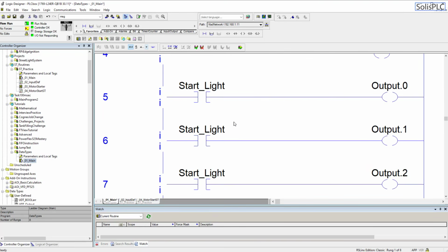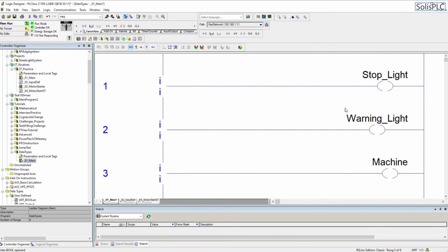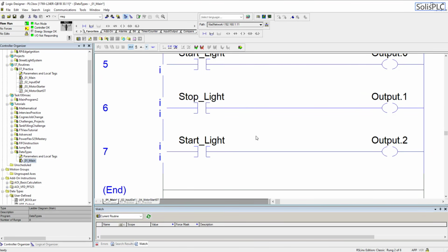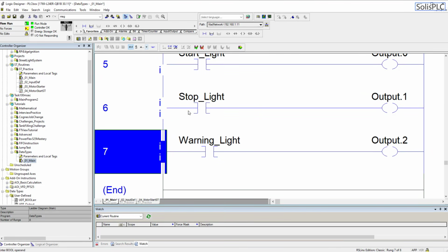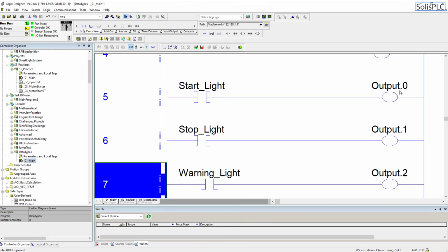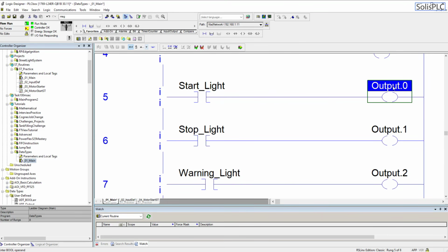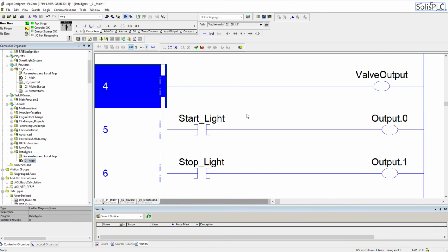And I might not be explaining this extremely well, but ultimately what's happening here is that if you were to, for example, change this card, so this could be, you know, output 0, output 1, output 2, and for whatever reason you have this output card that fails on your PLC or needs to be migrated, well, you need to readdress each one of these tags individually. Now, if you were to create an array which would be used as a buffer from each one of those tags, then that process would become much simpler.